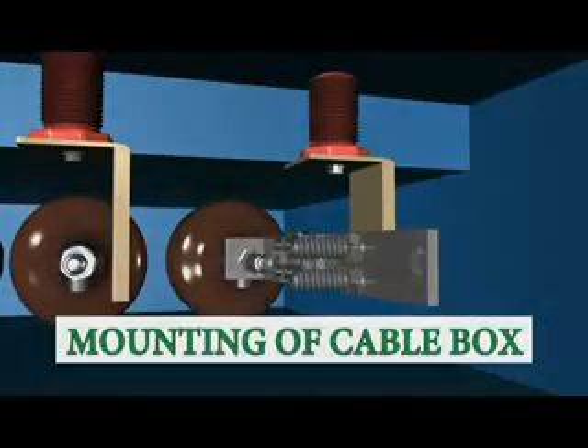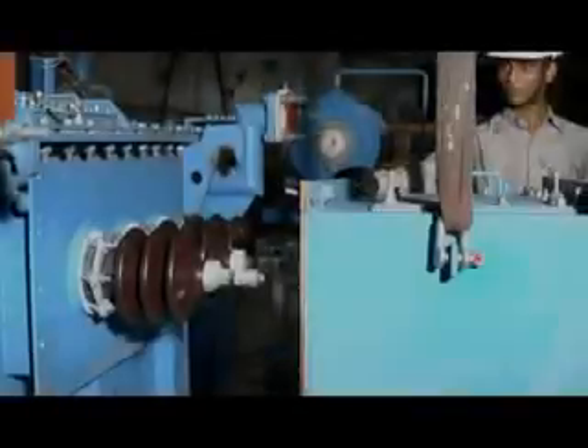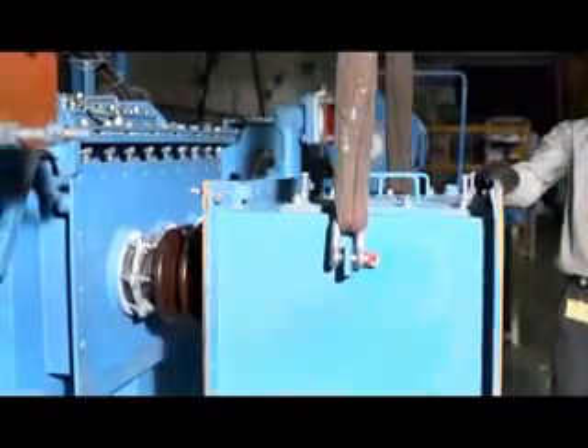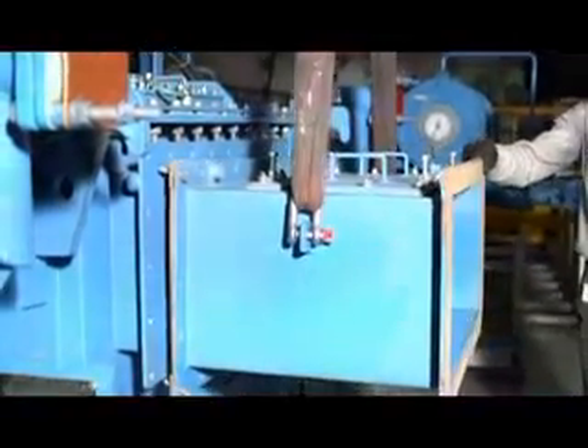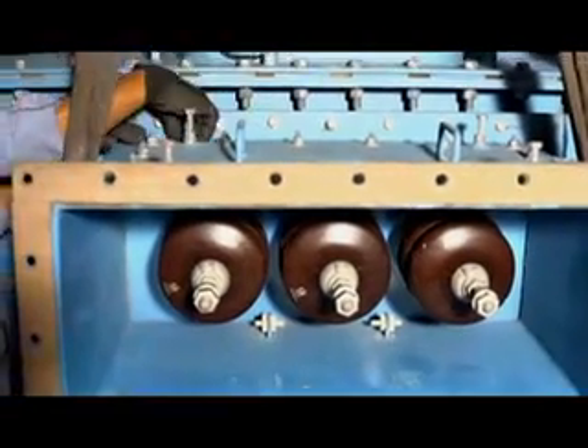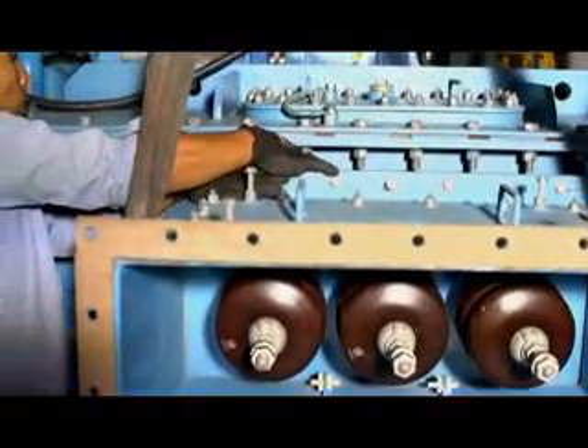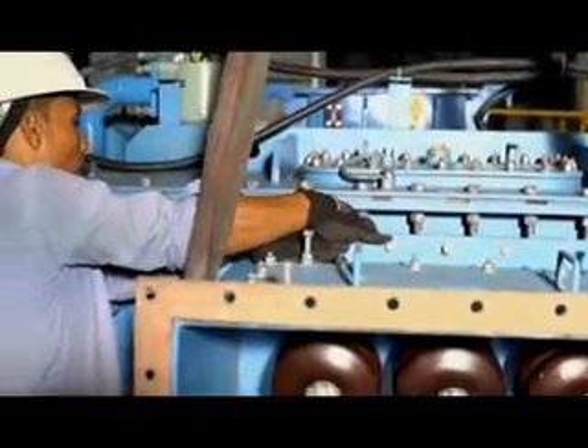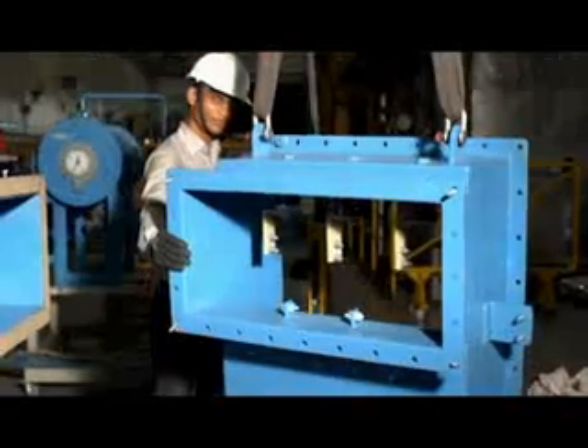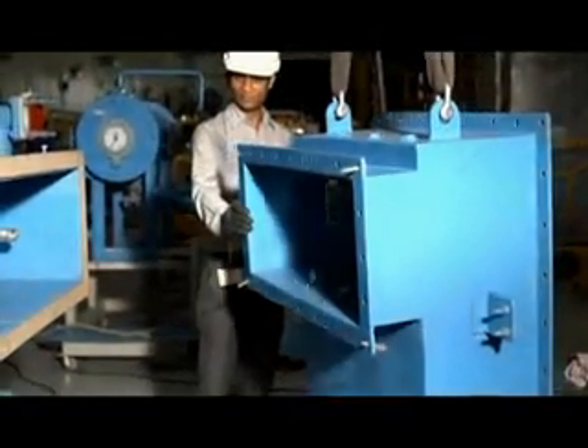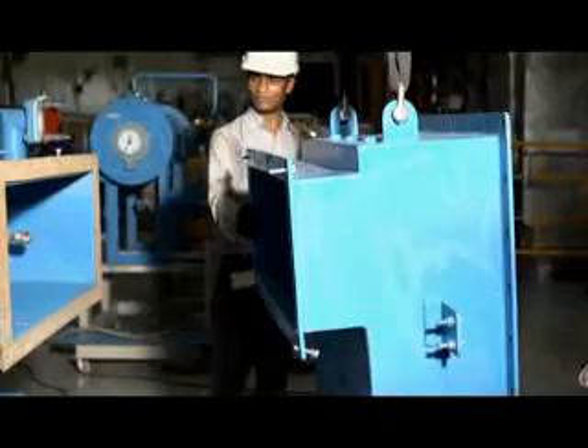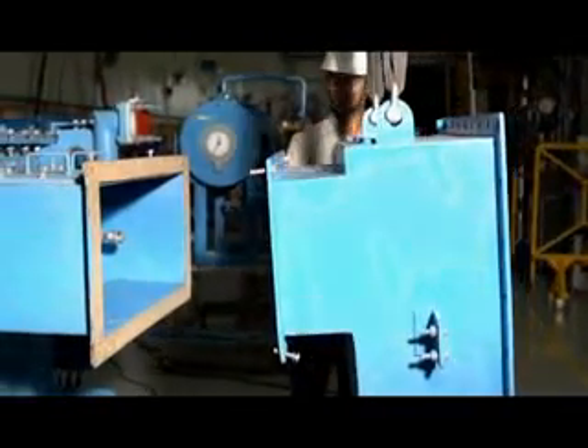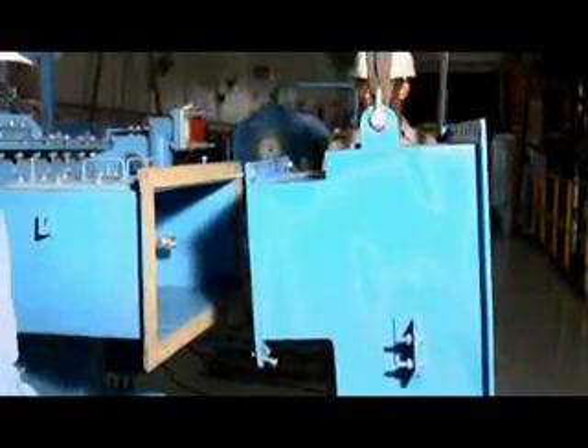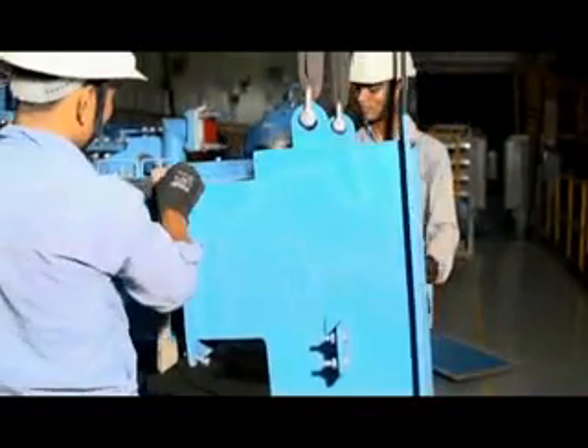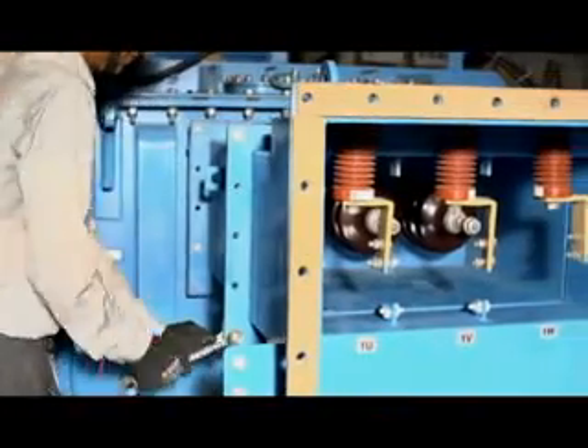Cable box. A cable box is generally provided in indoor type transformers. The purpose of mounting a cable box is to provide an enclosure to the transformer terminals and to prevent any damage or mishap from foreign particles. There is a cable entry gland plate at the bottom of the cable box and a copper bus bar with flexible on the upper side of this cable box to facilitate termination of cables and also provide mechanical support.